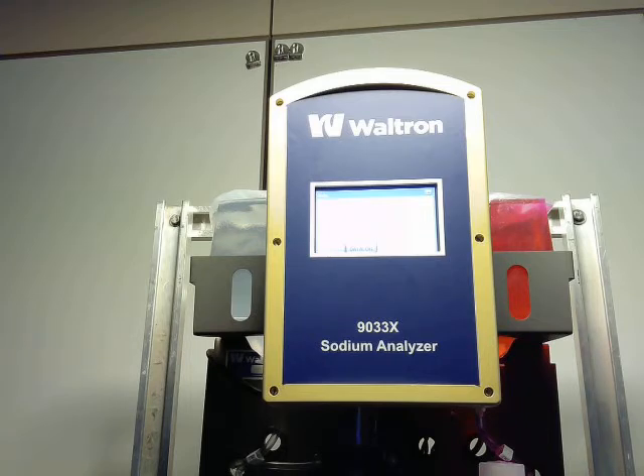Those are the two biggest, first things to look for with your slope. Obviously, if you get a slope of 0 or something like that, it probably means you're out of standards. It's seeing the same standard for both solutions. So it could be a solenoid failure or something like that.